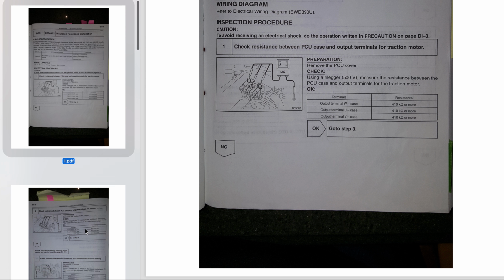Then it has you remove the cables to the traction motor, and I capped these off so that they're not touching anything. Then you're checking these terminals here. That has isolated the cables going down to the traction motor. So if the fault existed in there, you would suddenly see your resistance go up to the 410 kiloohms or more. In this case, when I checked it here on all of these, it was still less than 100 kiloohms. So that means it's still not good.